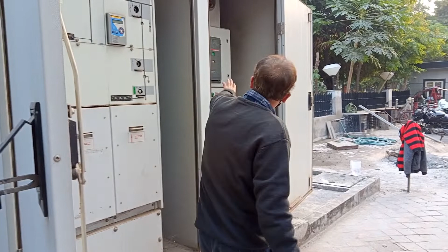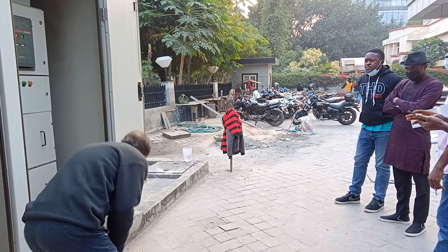Are you getting my point? There are outgoings. So the outgoings go via these breakers, 11 kV then step down to 430 volt 3 phase, and those outgoing cables are going to the LT panels. The basement, we'll show you next. Incoming is from these 4 poles you have seen, right? HV side, LV side, and then the LV side goes to the low voltage basement. Fundamental idea should be very clear. Any doubt? Preliminary or basic engineering clear?